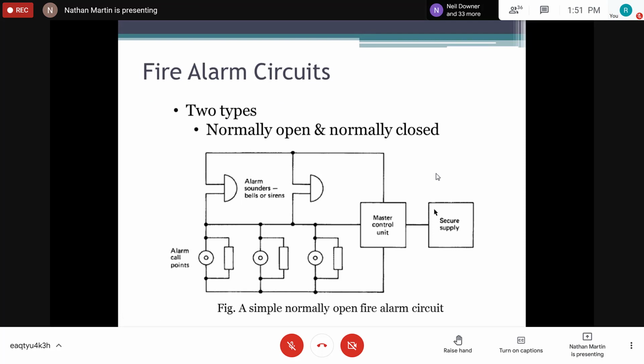So we say there are two types of fire alarm circuits that you need to know about: the normally open and the normally closed. Now, the one shown here is a normally open, simple circuit. So we just show you a simple diagram, right? Based on the diagram, we can give a brief operation of the circuit. If any one of these devices is activated, the alarm sounders will sound, right? So they are actually placed in parallel rather than in series. In a normally closed situation, they are actually wired in series rather than parallel.